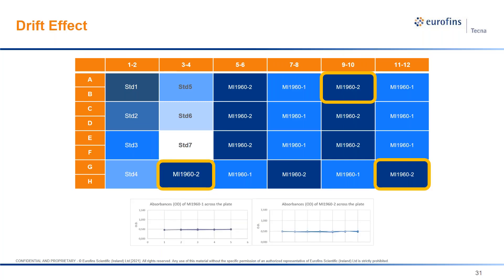Some automatic analyzers have intrinsic limitations in the number of determinations that can be run, as the machine can be slow and implicates operational delays. I wanted to run a full plate of 96 wells, running alternating reference materials to see if the assay result had an impact on sample position. As visible in the graph, all results were compact despite the sample position variation, so I was confident there was no drift effect.